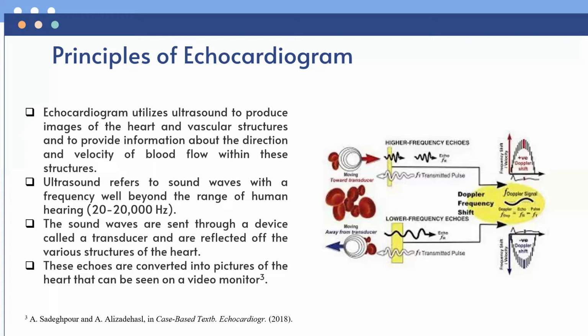the highest frequency that can penetrate to the structure of interest is generally preferred for M-mode, 2D and 3D echocardiogram. The opposite is true for Doppler and color flow mapping, in which lower ultrasonic frequencies generally provide better information. Low frequency sound waves have deeper tissue penetration but lower image resolution. High frequency sound waves have less tissue penetration with higher image resolution.